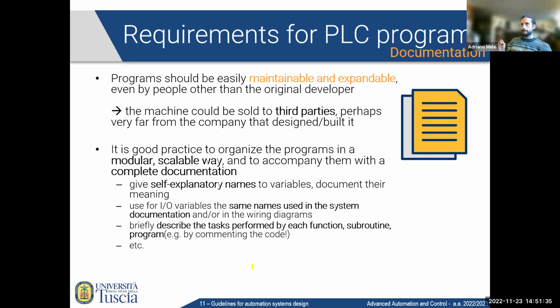Third, IO variables should have the same names in the system documentation, in the wiring diagrams, and in the program. So if your motor is called motor 1, then you should have a variable in your program called motor 1, and your wiring diagrams should report the motor 1 tag.